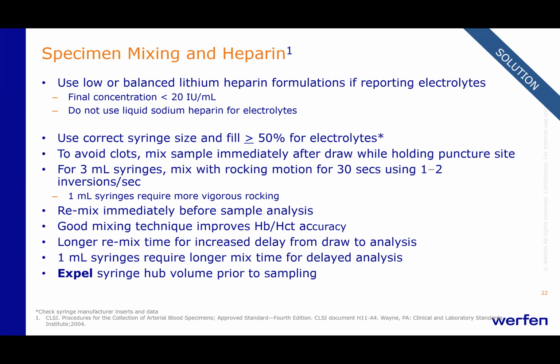Use correct syringe size and fill to greater than 50% of capacity for electrolytes. And some manufacturers claim that you don't have to fill the syringe to more than 50% of capacity. So please read the inserts on your syringes. This is particularly important for neonatal applications when you're using 1 ml syringes.